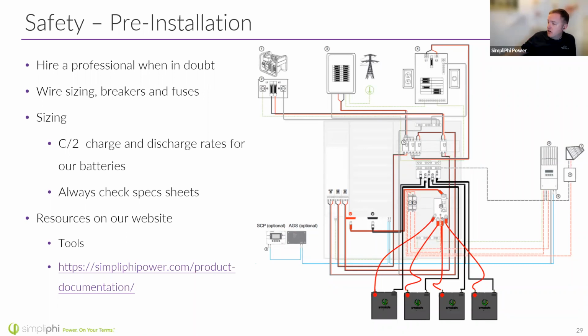Let's make sure we get out our code books. I'm looking over here at my code book. Make sure we size the ampacity and voltage drop of our conductors, and protect them with the proper breakers and fuses. Understand that our batteries have a C/2 discharge rate, meaning the rate you can continuously charge or discharge is C/2. So if it's a 75 amp hour battery at 48 volts, you can charge or discharge it continuously at 37.5 amps at 48 volts. We do have the ability to surge higher than that at a 10-minute interval to get other loads started, but always check those spec sheets.